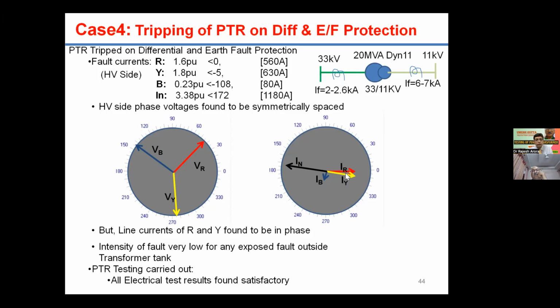Now, this was quite an interesting case, because if there is a fault on the LV side of the transformer, my current will flow from the HV R and Y phases, and they should be 180 degrees out of phase. But here we were getting currents which were in the same phase. Now, the intensity of this current is also very low.